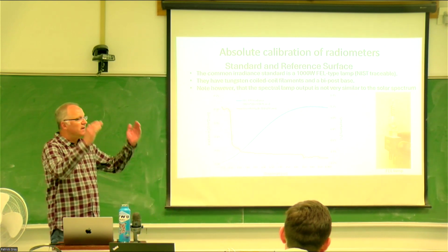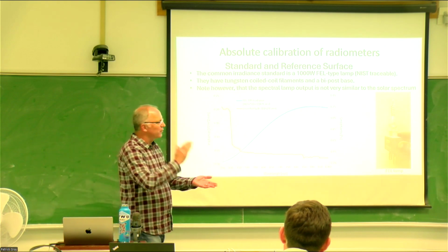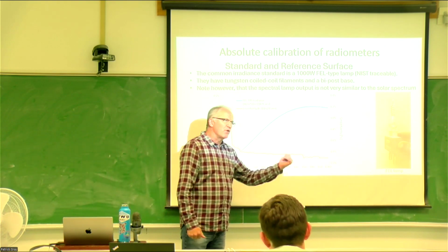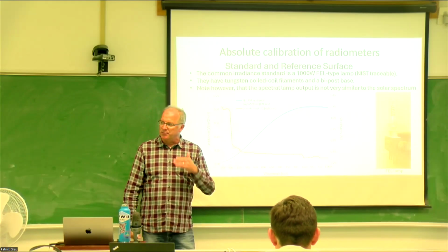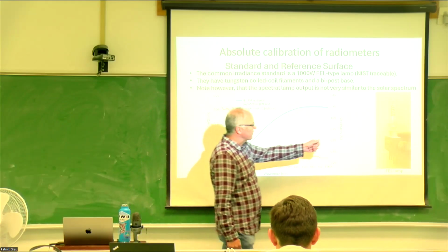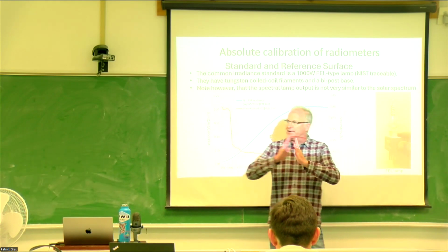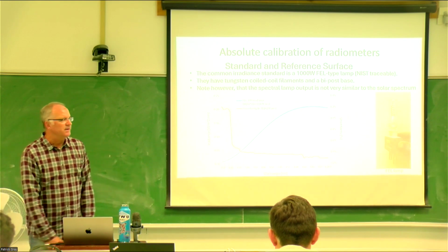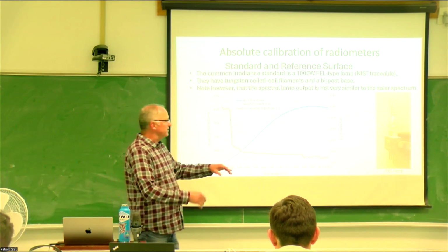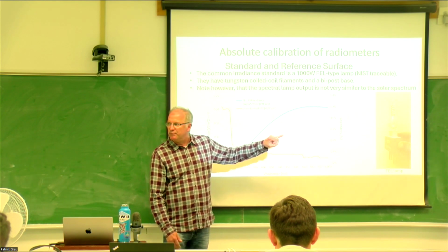And again, we're going to get to this. You're trying to really reduce all the uncertainty and get as accurate a calibration as you can. So if I put my thumbprint on here, all of a sudden the radiance output changes massively. You've got grease on it, so all that adds in. Now your spectrum is going to have wiggles on it.